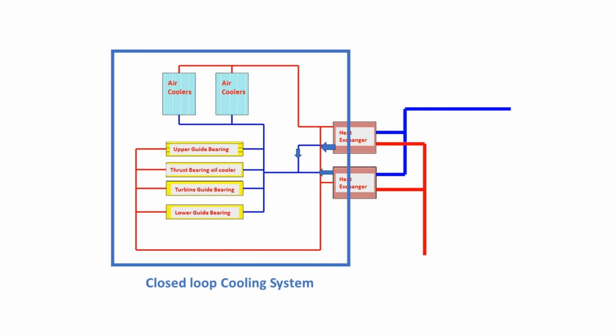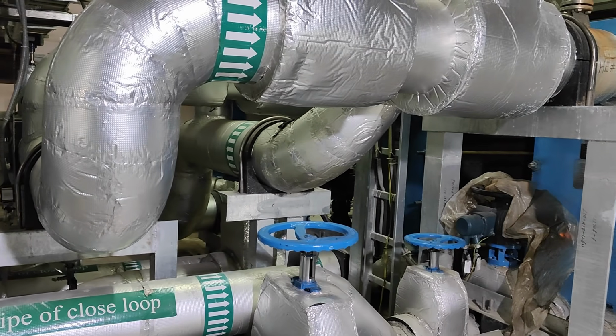Simple. But the closed loop is different. This loop contains clean, treated water. This clean water never mixes with river water. Instead, it circulates continuously inside the powerhouse, cooling sensitive equipment safely. So the real engineering trick is that dirty river water removes heat from clean cooling water without the two waters even touching each other. And the machine that makes this possible is called the heat exchanger.